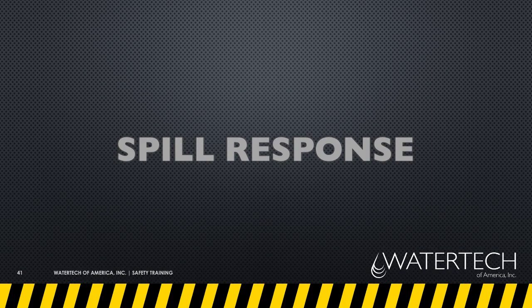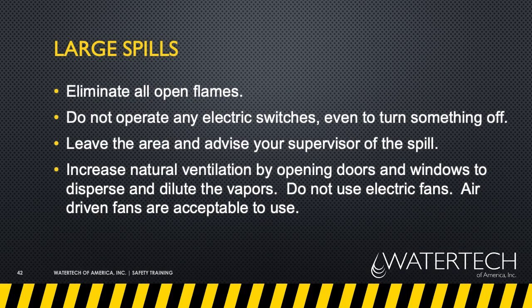Now we will go over what to do in case of a spill. For large spills, eliminate all open flames. Don't operate any switches, even to turn something off. Leave the area and advise your supervisor. If possible, increase natural ventilation by opening doors and windows. Air-driven fans are acceptable.